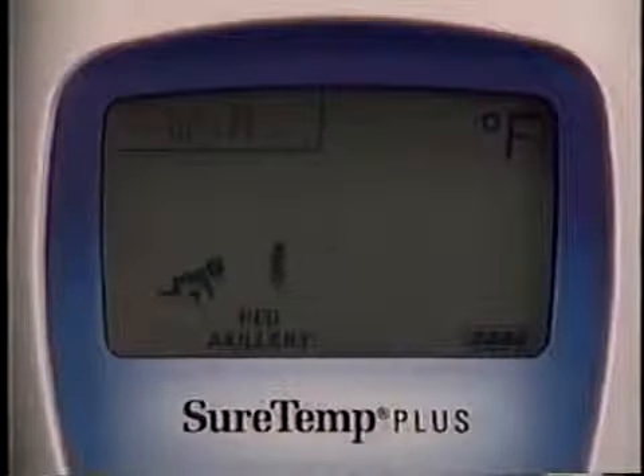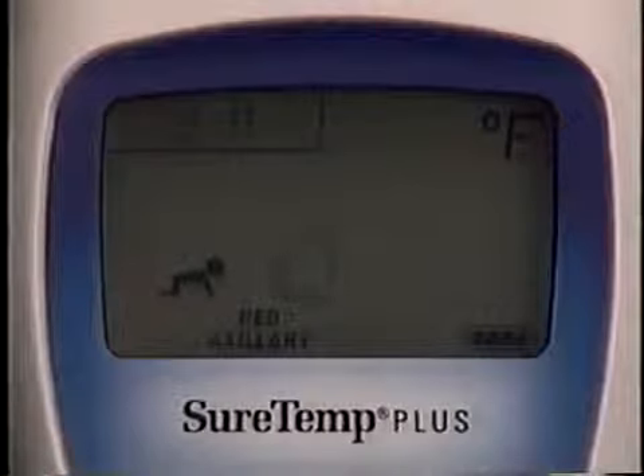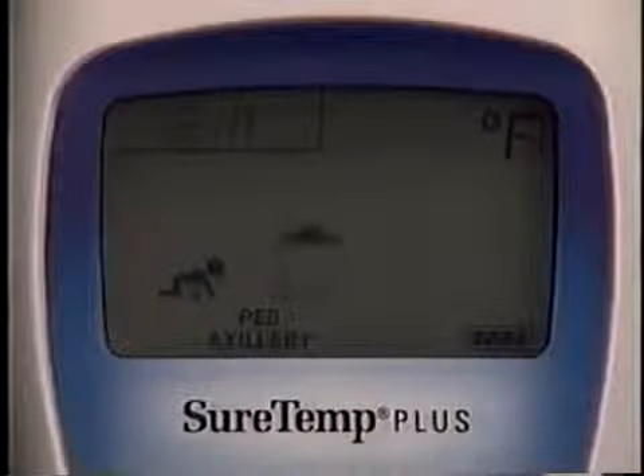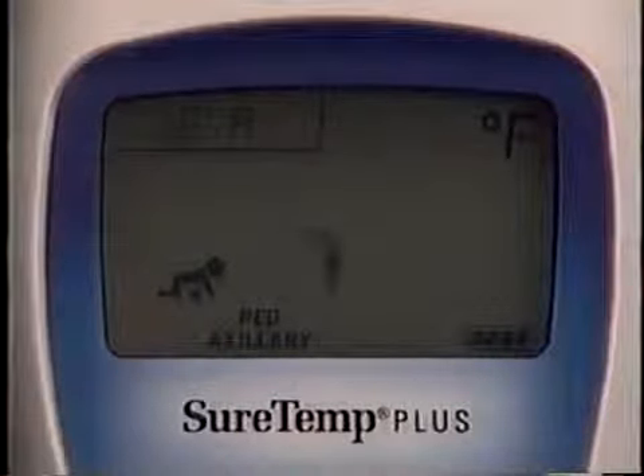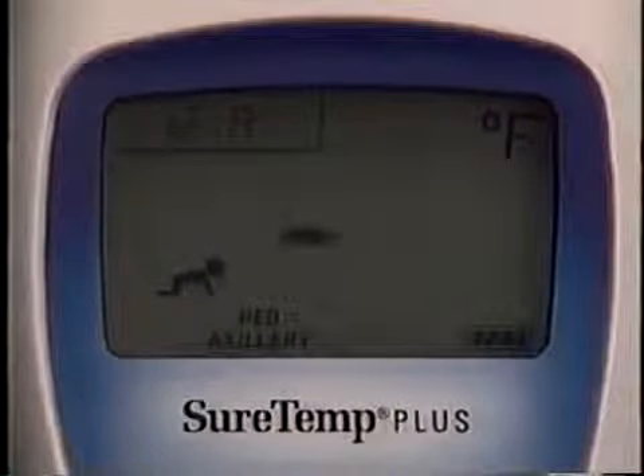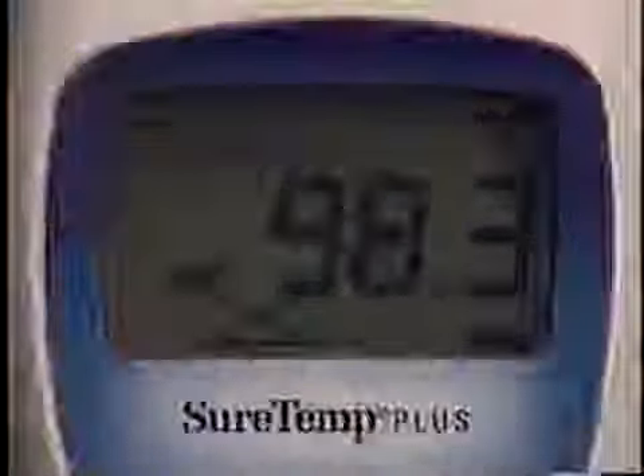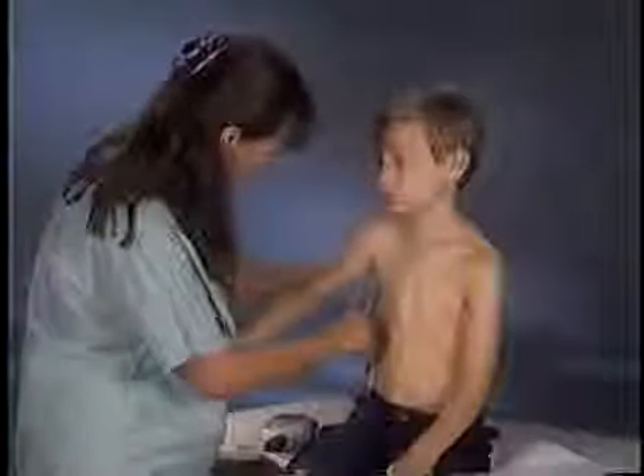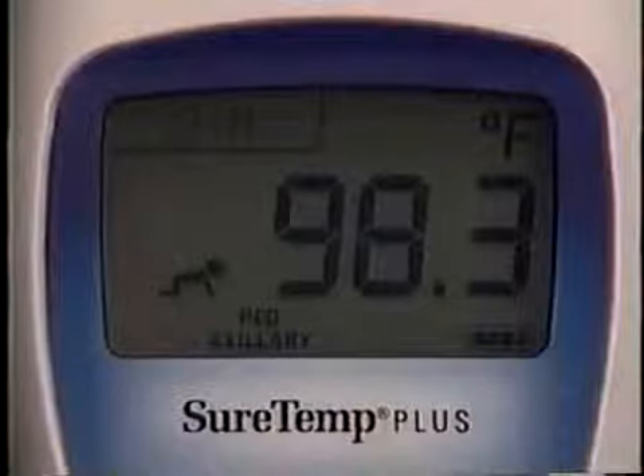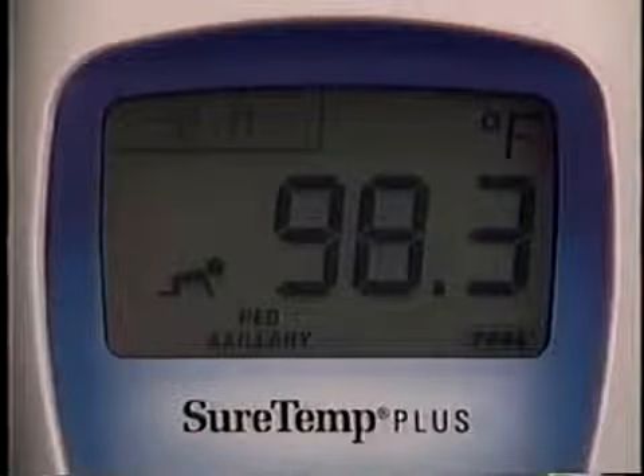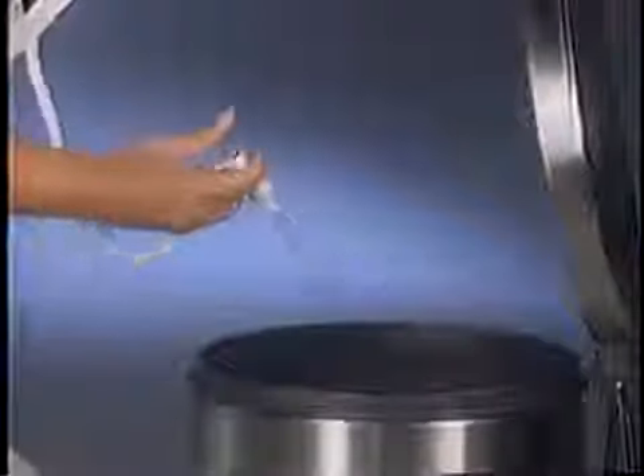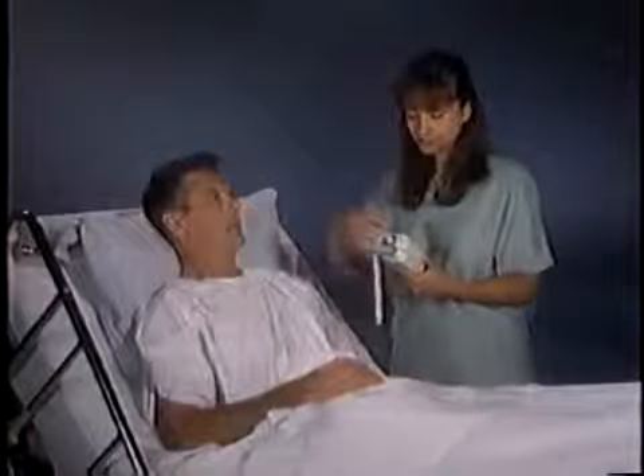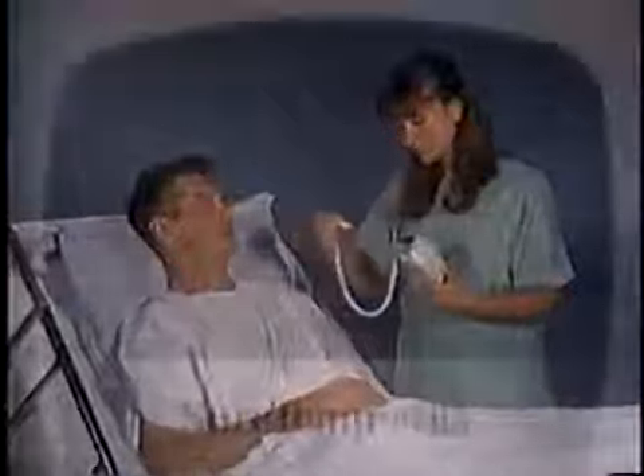When the final axillary temperature has been reached in about 10 to 13 seconds for pediatric patients and 12 to 15 seconds for adults, the unit beeps and the temperature displays. Remove the probe from the patient's axilla and note the temperature, which remains on the display for 30 seconds, or until you place the probe back into the well. Eject the probe cover and place the probe back in the well. Adult axillary temperatures are taken the same way, using the adult axillary mode.